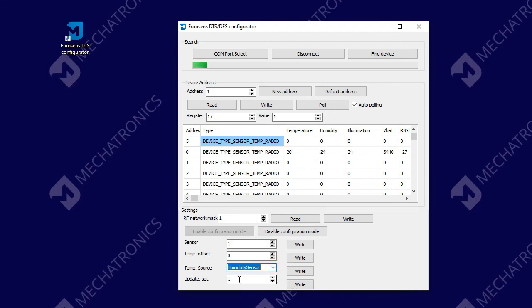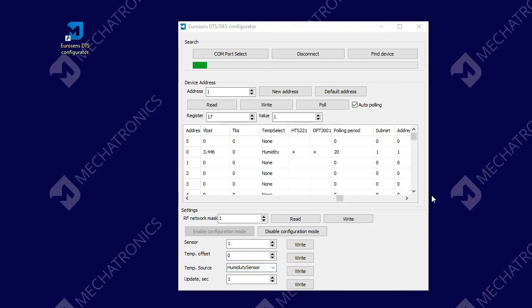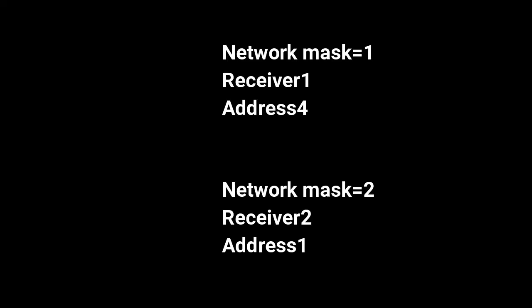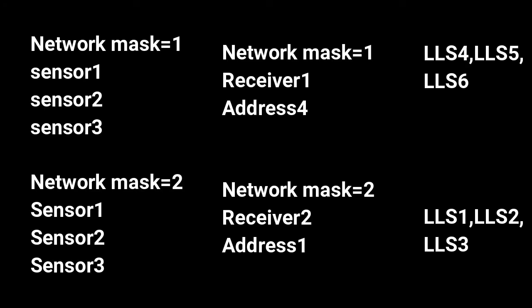Update parameter defines how often sensor sends the data. A higher frequency of updates leads to a faster battery drain. Receiver collects data from all available temperature sensors. To divide receivers or sensors into groups, we can use the RF network mask parameter. The receiver with network mask number 2 doesn't read the sensors with network mask number 1.